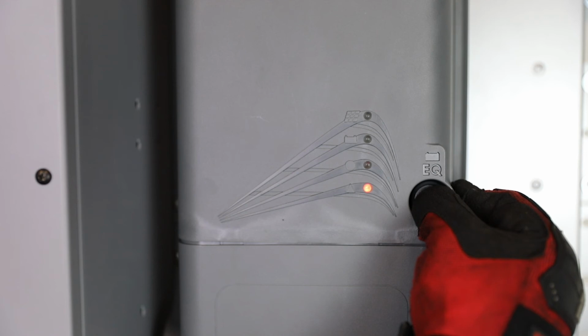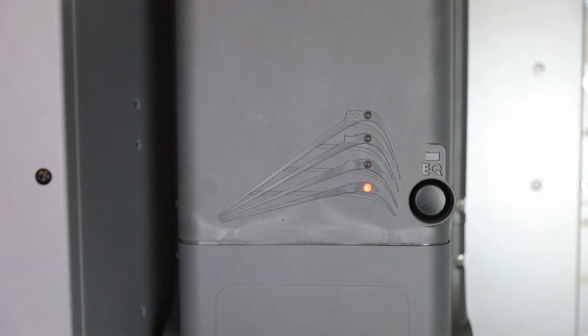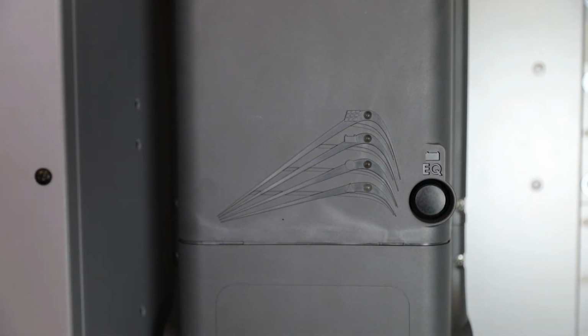You may now release the EQ button and turn off the battery source breaker. Turn the battery source breaker back on. The FM100 will now sense the battery voltage and use this reading to determine the new nominal system voltage.